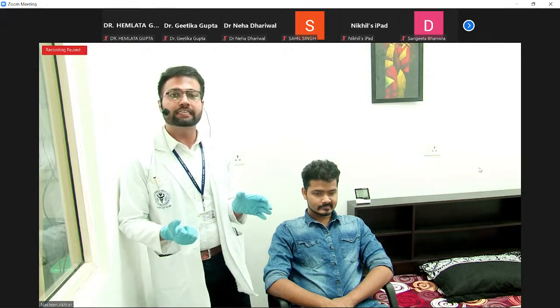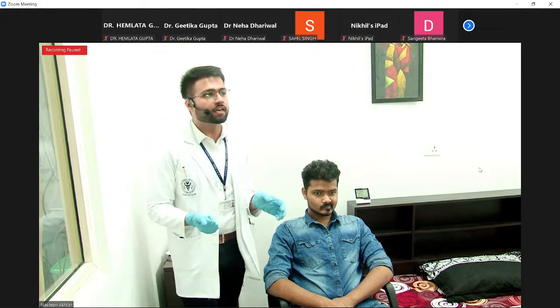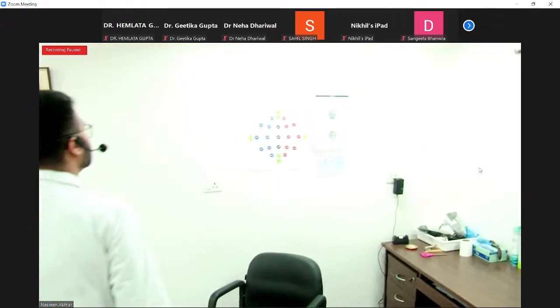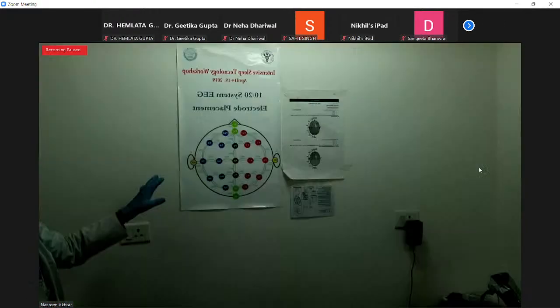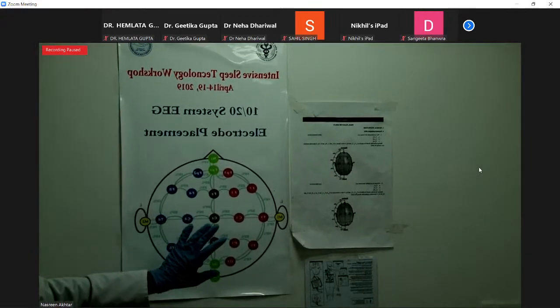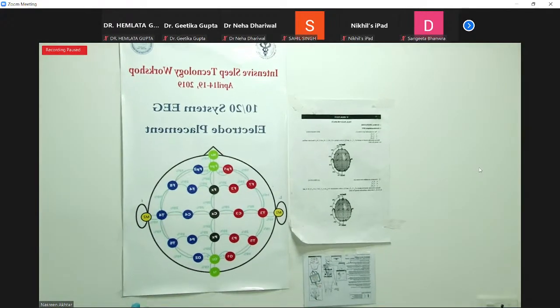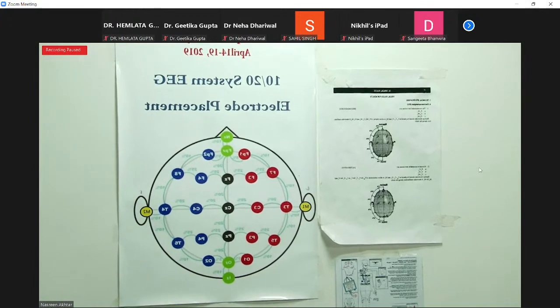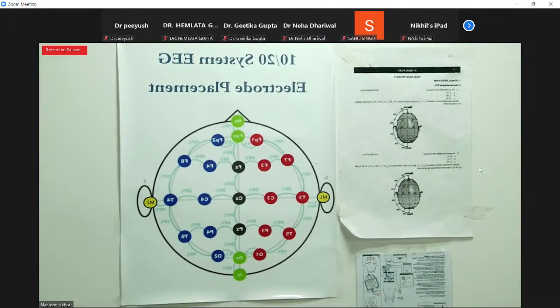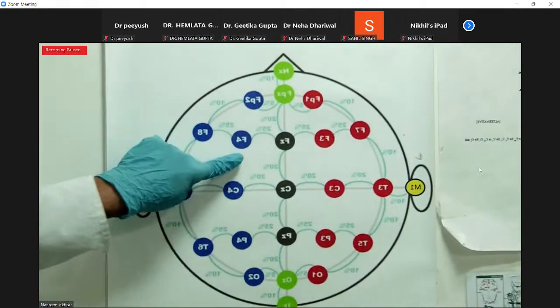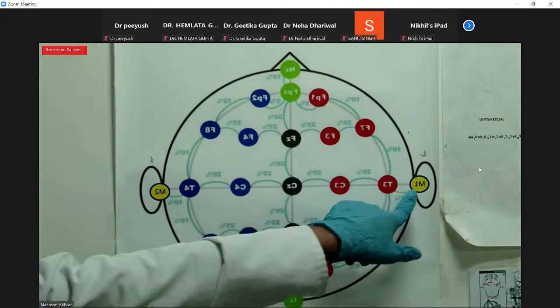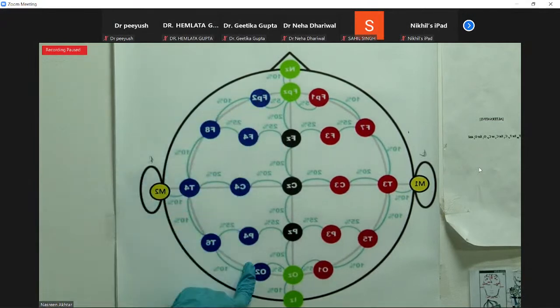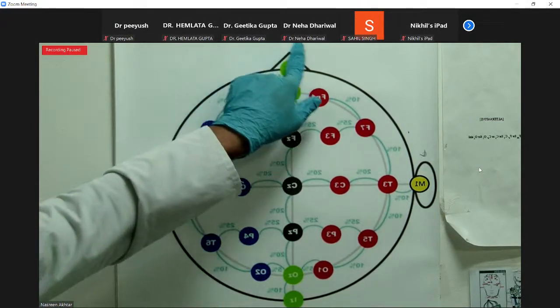Firstly, we will start with the EEG electrode placement. As you can see there, can you please move the camera? This is the 10-20 system, which is also shown to you by the faculty. This is the standard electrode placement, which is recommended by the American Academy of Sleep Medicine. The montage consists of 6 channels: F3, C3, O1, F4, C4, O2. CZ will be the common reference for everyone. M1 is the reference for the odd side and M2 is the reference for the even side.